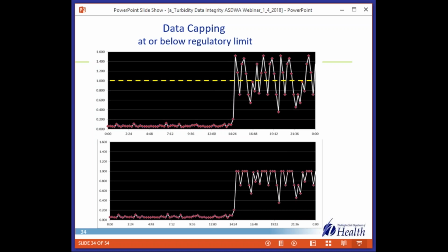If they had their output set for 1.0 equals 20 milliamps, this same excursion shows up differently in the SCADA system. So in this case, they're still running along great. Their coagulant feed pump still clogs, but now turbidity somehow miraculously is held at 1 and then bumps around, still out of control, but never exceeds.